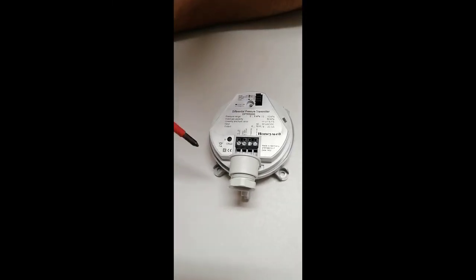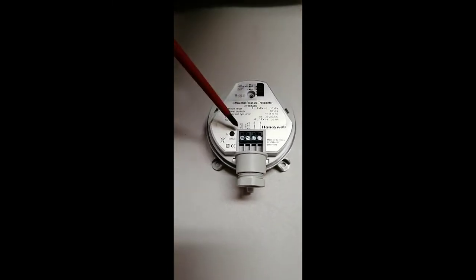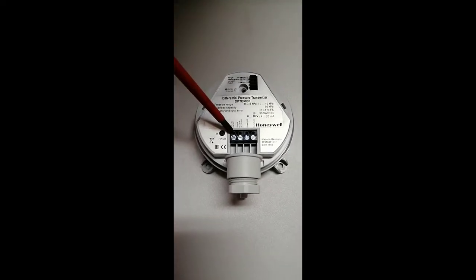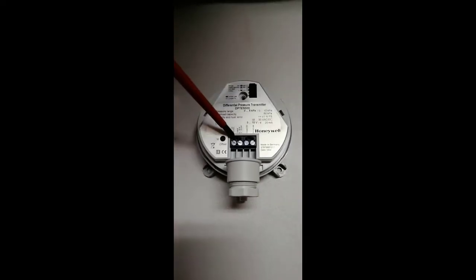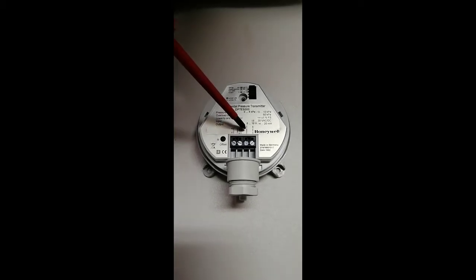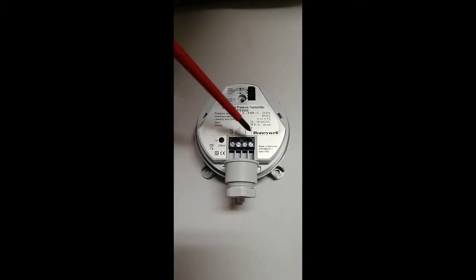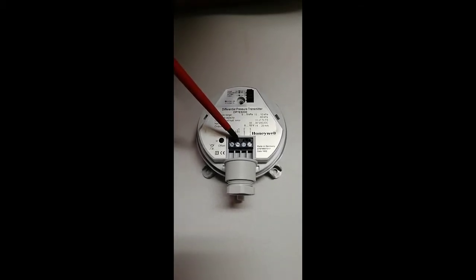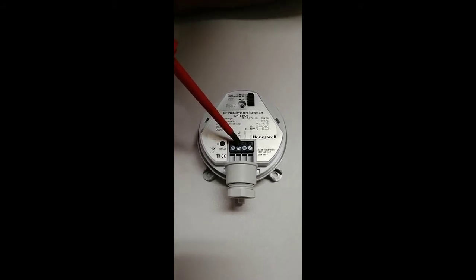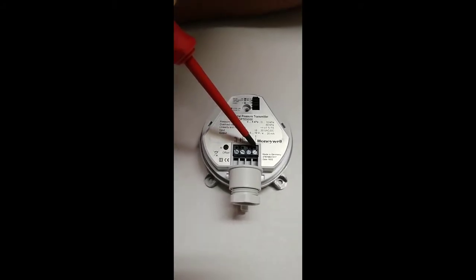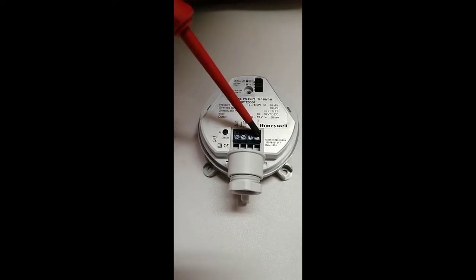Regarding connections, first of all we need a power supply. Okay, this number 1 is for power supply. We can connect here 24 volt DC or AC, and the common will be the number 3 point, and we will get output signal on 0 to 10 volt signal on number 2. Okay, this fourth point is redundant, we will not use this point.